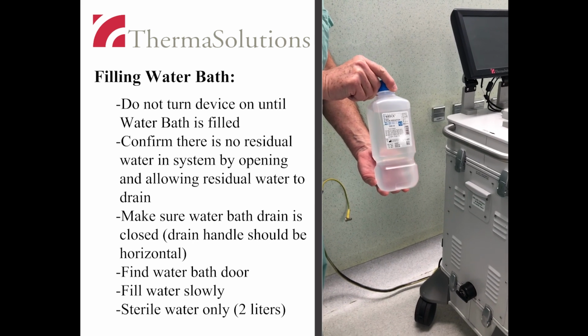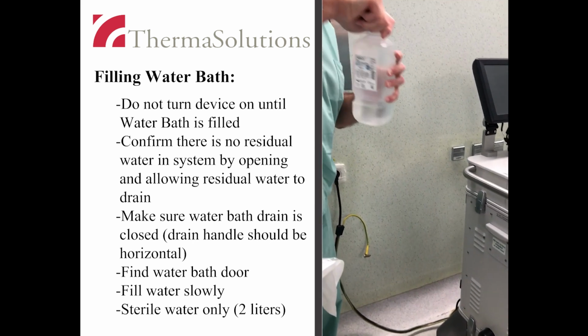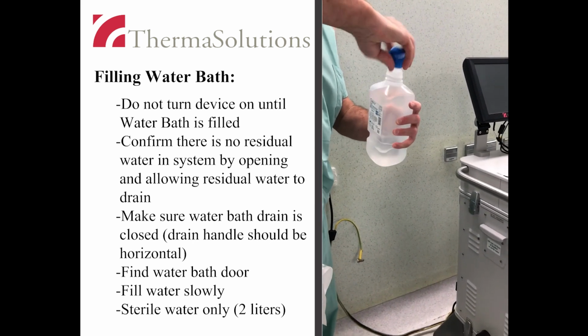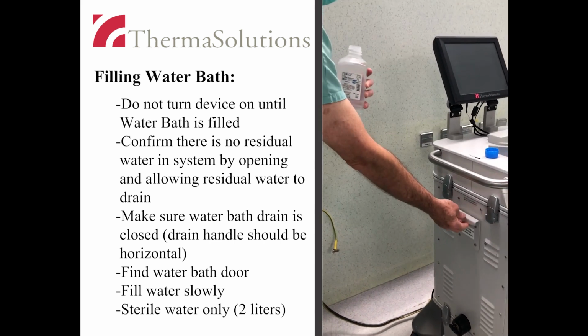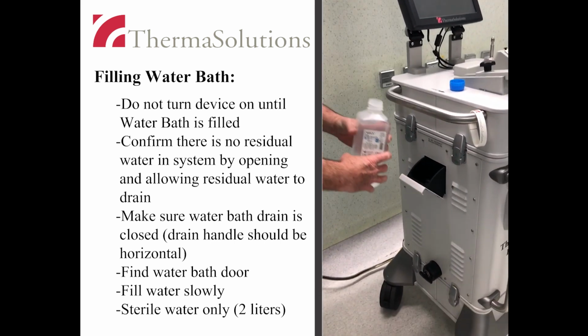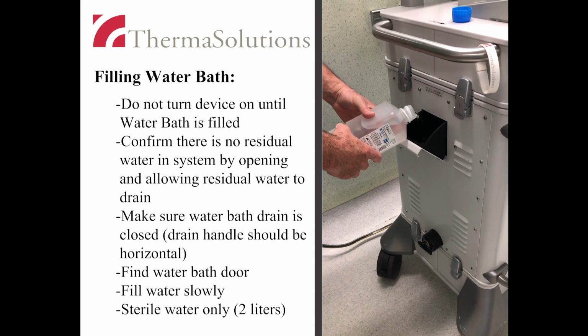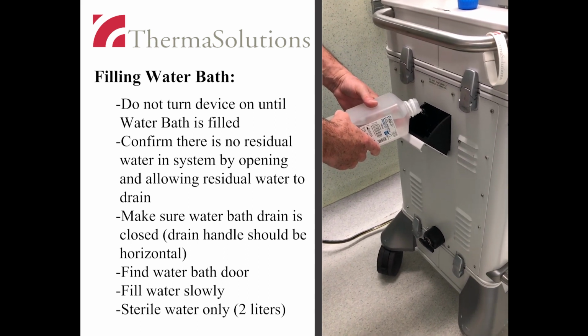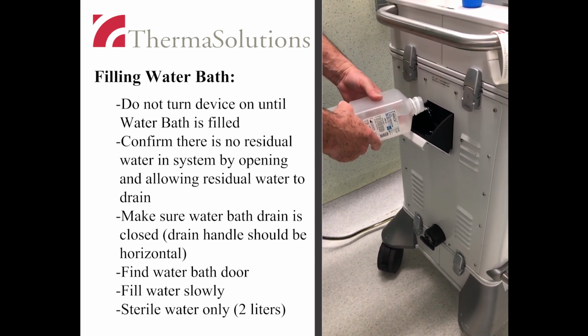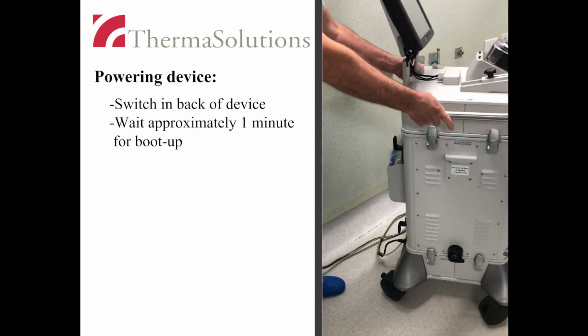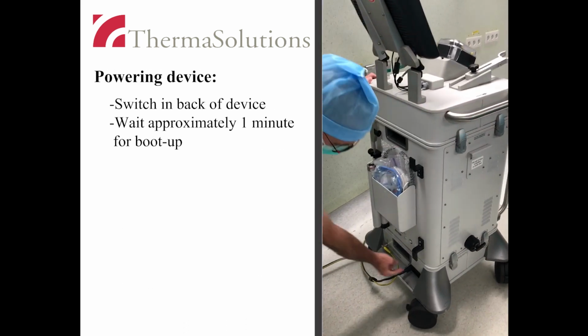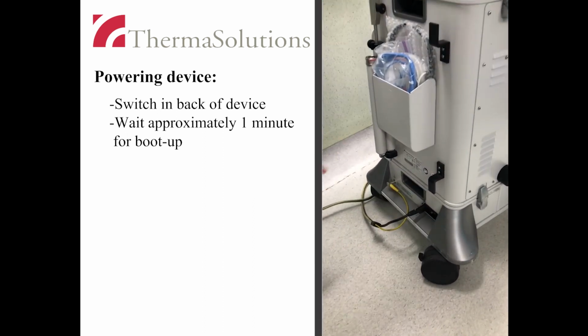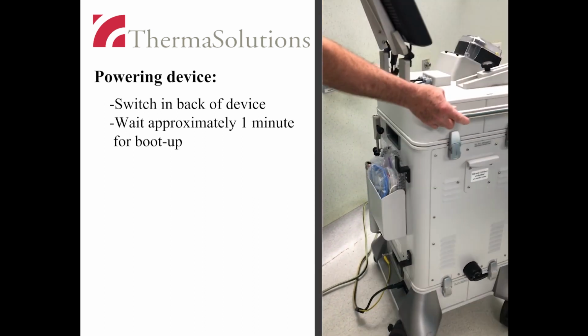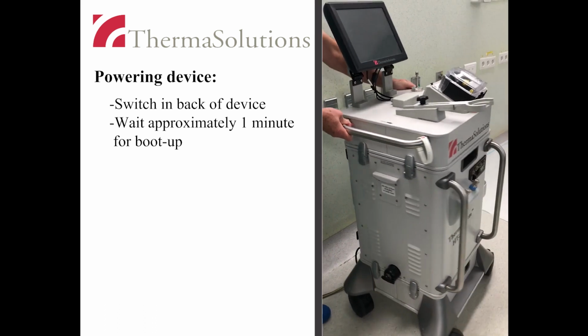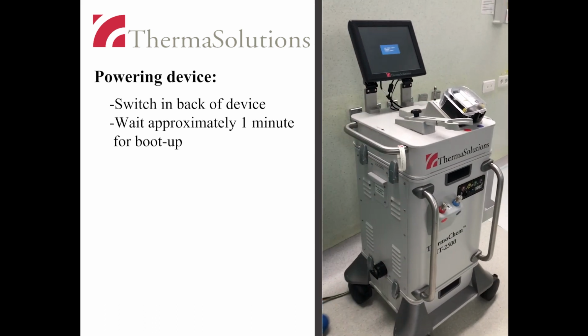The water bath should be filled prior to powering up. Open the water bath drain first to confirm the water bath is empty and have a basin to catch any residual water from a previous case. When the drain tap is closed, open the water bath door and slowly fill with 2 liters of sterile water. The power switch is on the back of the unit above the cord socket. Power the device on and wait for the monitor to show the boot up process. This should take less than 1 minute to complete.